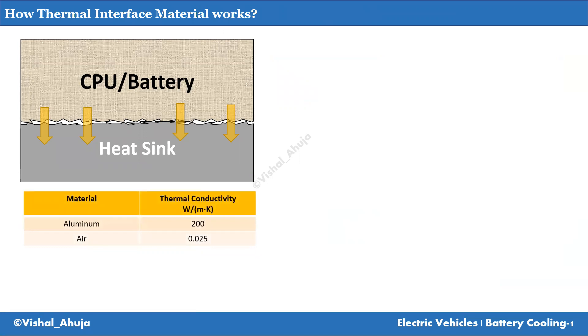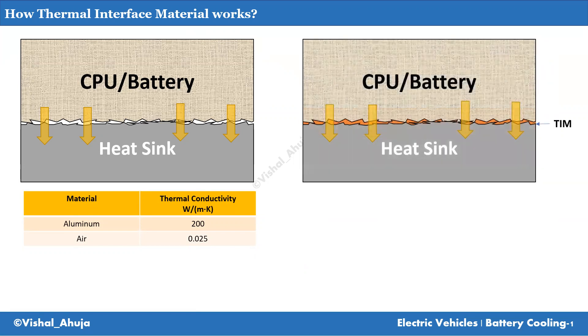If you see the conductivity of metals — in this case aluminum or copper — they have more than 200 W/m·K as thermal conductivity. But when these two surfaces come in contact, there is air between them because there are certain irregularities on the surface of metals; they are not completely flat. A major amount of the contact area is filled with air gaps, which creates a problem. To eliminate this, there is something called thermal interface material, which is filled inside and enhances the heat transfer.